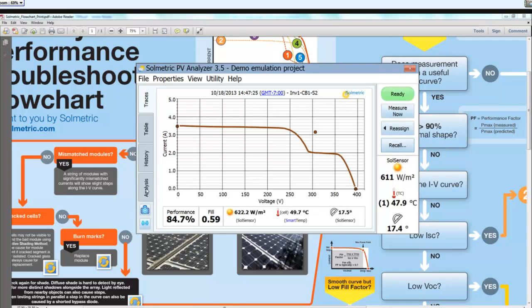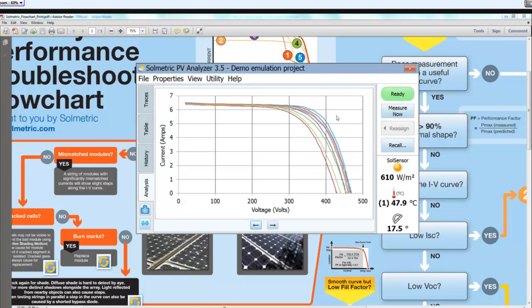You'll see there's an analysis tab in the software, and this is an example of what we could do: show a whole combiner box worth of IV curves in one plot. This would be useful when you're finished with a combiner, when you're commissioning, or doing a recommissioning because you're taking ownership of a system. You can measure your strings at the combiner, and then look at them and see how tightly they're bunched.